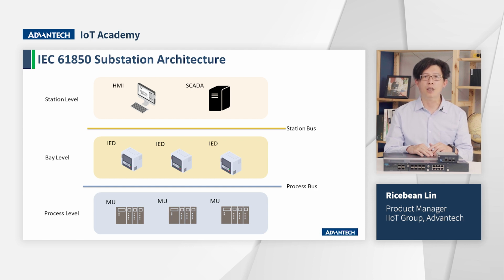To know each role in the substation, we can see the architecture. The IEC 61850 standard defines three levels. The first one is the station level, and it contains the station SCADA and HMI, used to control and monitor the station. The second level is the bay level, where we have the IED, and IED means the new name of the relay, to reflect the capability to take a decision based on the logic and the information collected from the process level device. The last one is the process level, where we have switchgear like a circuit breaker and the switch, and the instrument device like a current transformer and the voltage transformer.